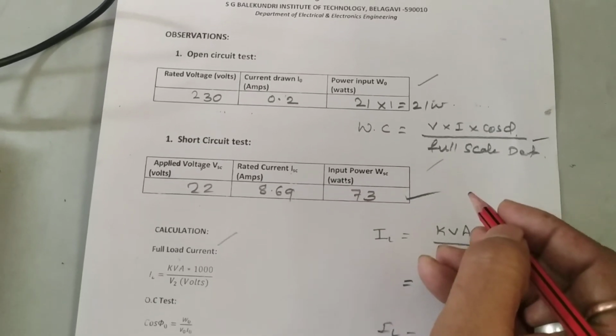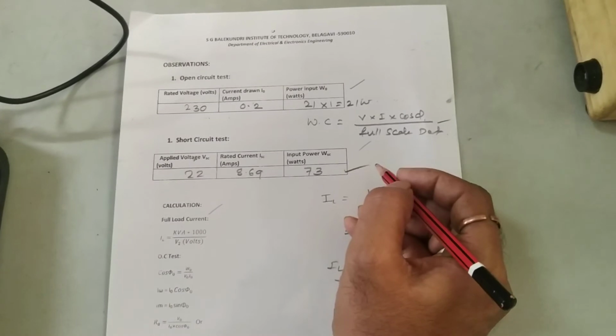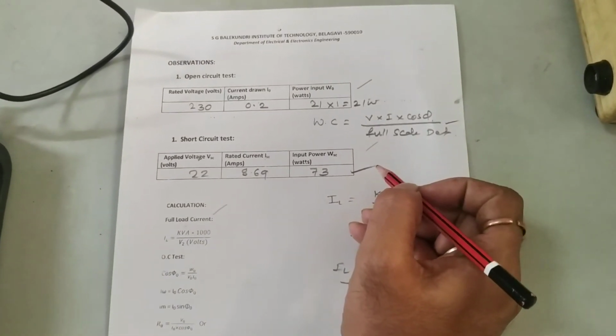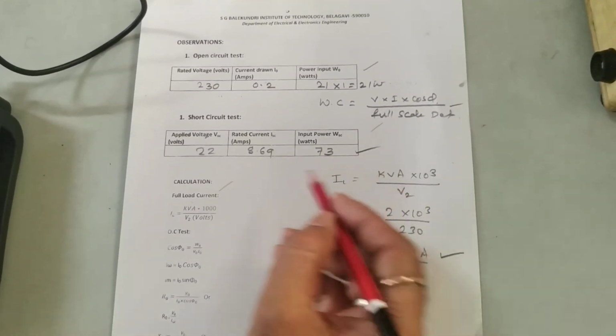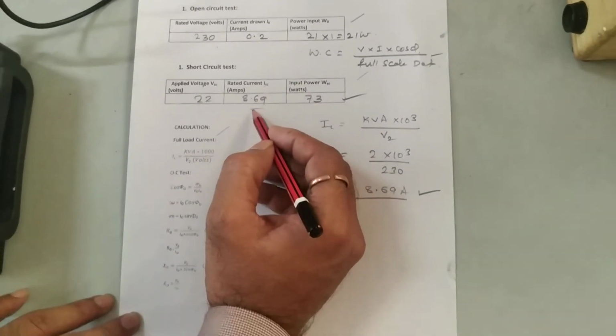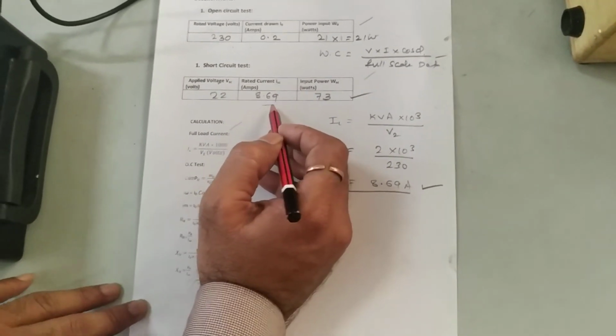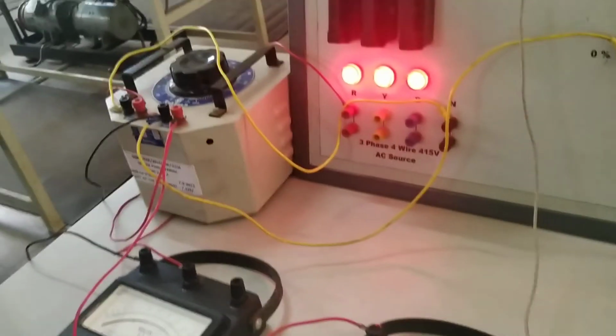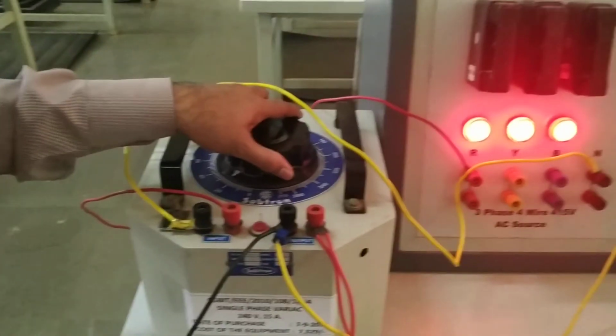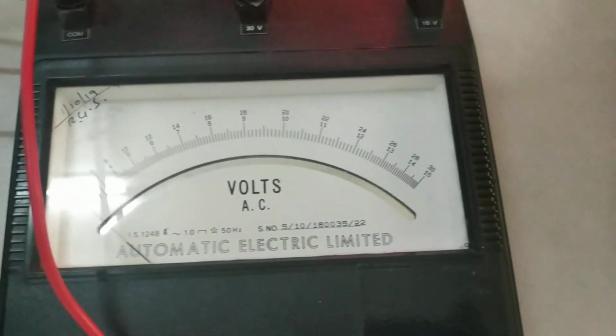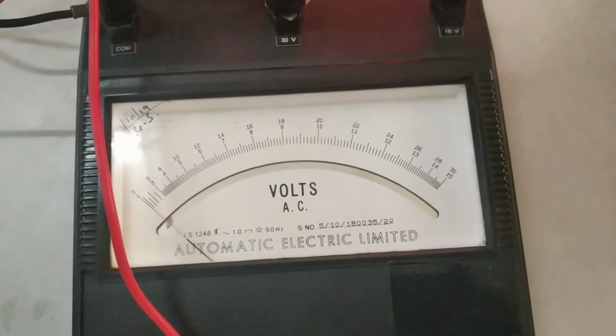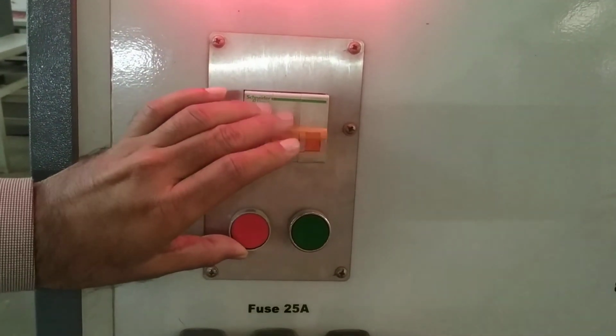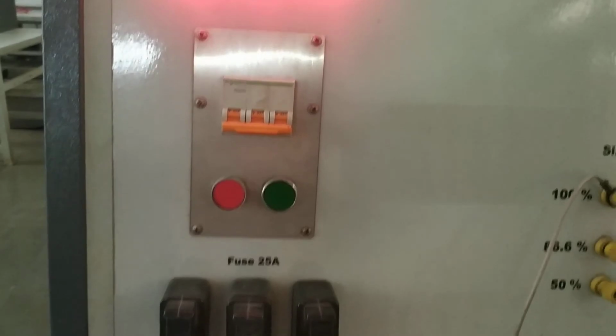Like this we can conduct an SC test on the single phase transformer. We need to take care about the current flowing, because we conduct this test depending upon the rated current of the transformer. After that, we need to reduce the voltage with the help of the auto transformer. It means we bring it back to zero position and switch off the main supply. Like this we can conduct the SC test on a single phase transformer.